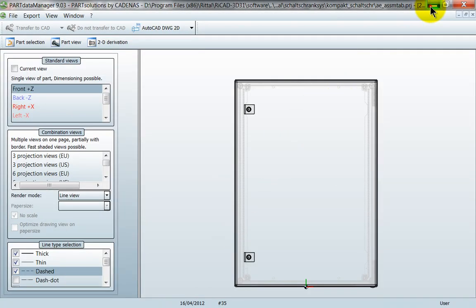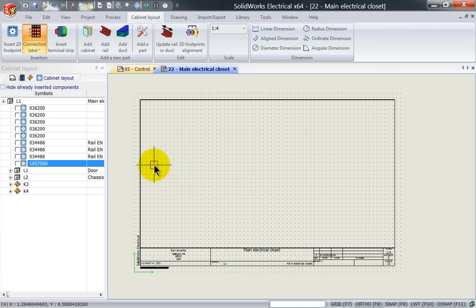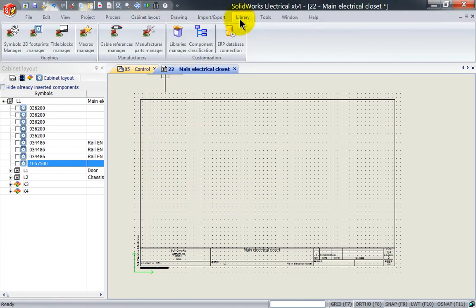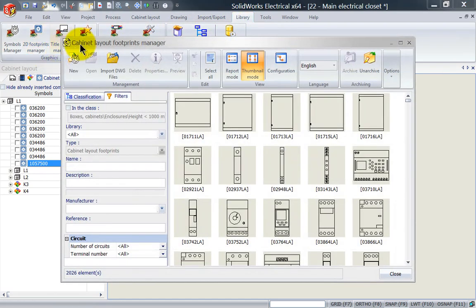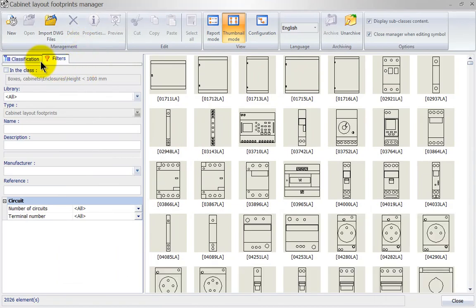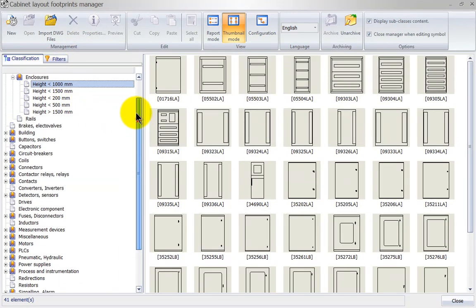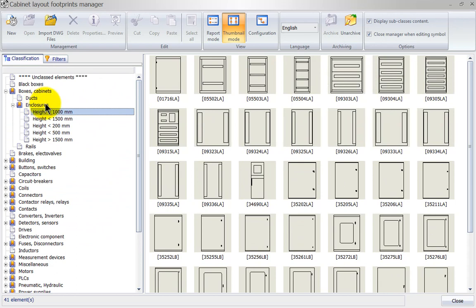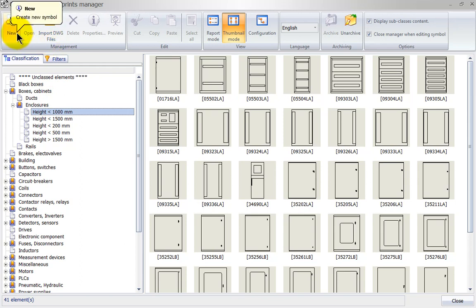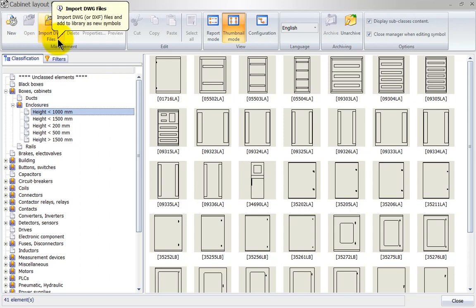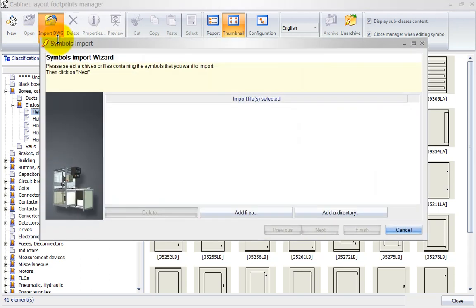Once that is generated, inside SOLIDWORKS Electrical we will go to the Library tab and left click on 2D Footprints Manager. We're going to go into the classification Enclosures Below 1 Metre, and instead of selecting New — which would allow me to draw the whole symbol from scratch — I'm going to import it from a DWG file, so left click Import DWG.